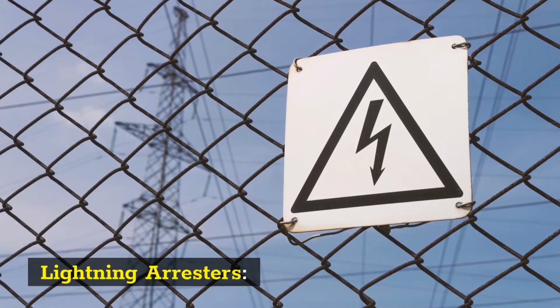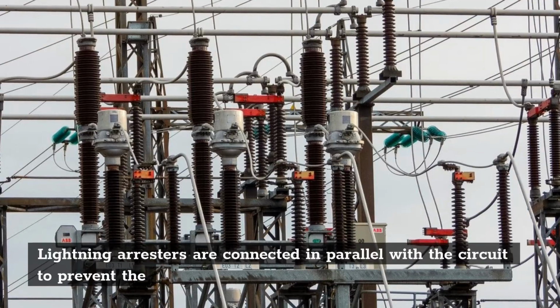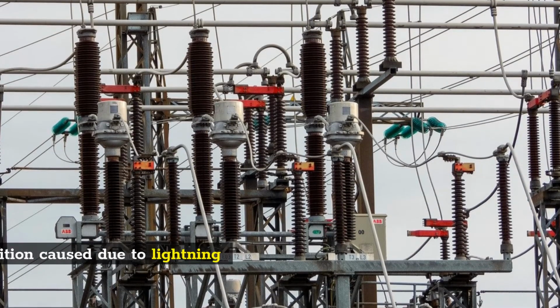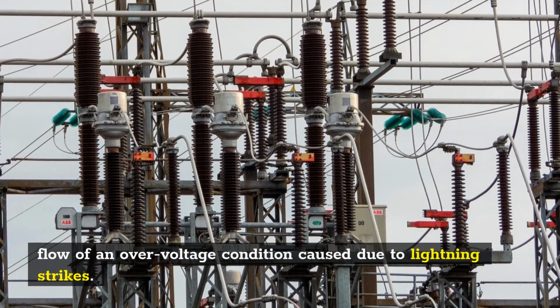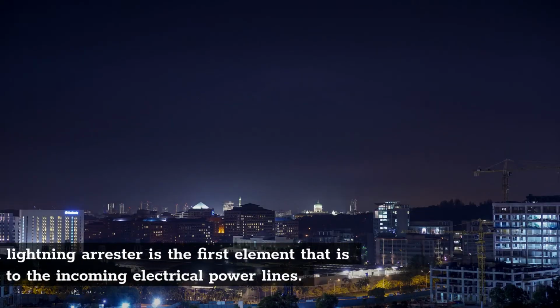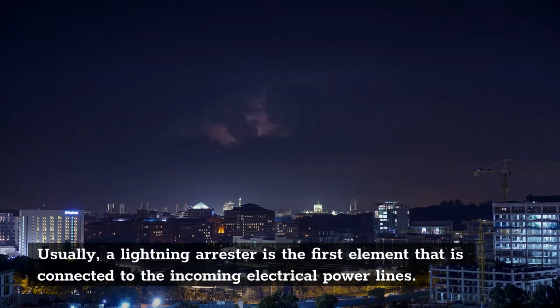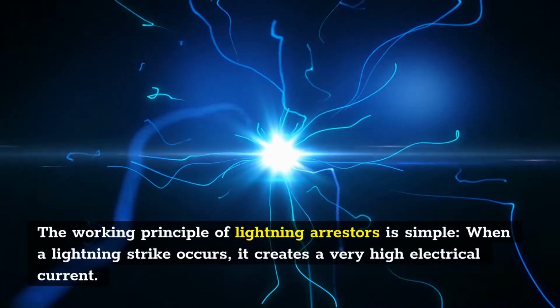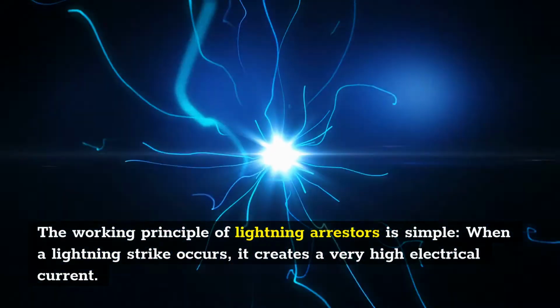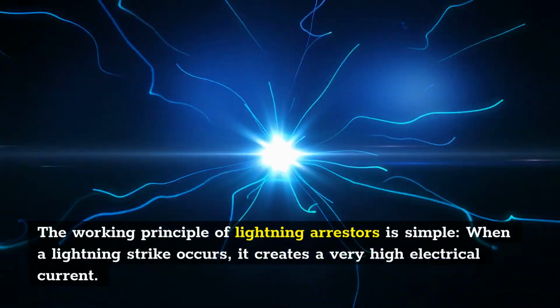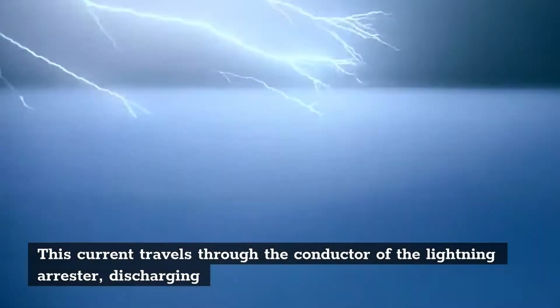Lightning arresters. Lightning arresters are connected in parallel with the circuit to prevent the flow of an overvoltage condition caused by lightning strikes. Usually, a lightning arrester is the first element that is connected to the incoming electrical power lines. The working principle of lightning arresters is simple. When a lightning strike occurs, it creates a very high electrical current. This current travels through the conductor of the lightning arrester, discharging it and allowing the current to flow to the ground.